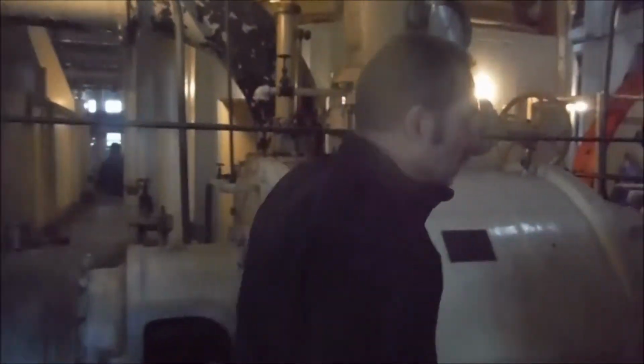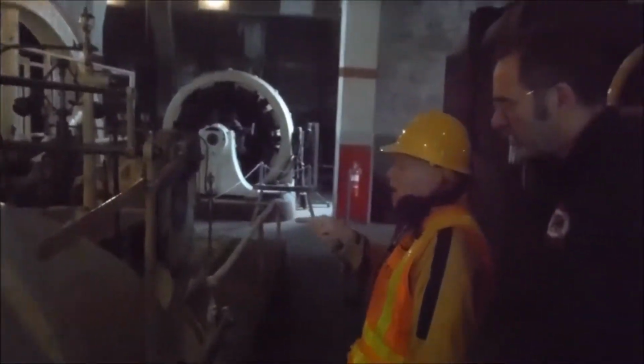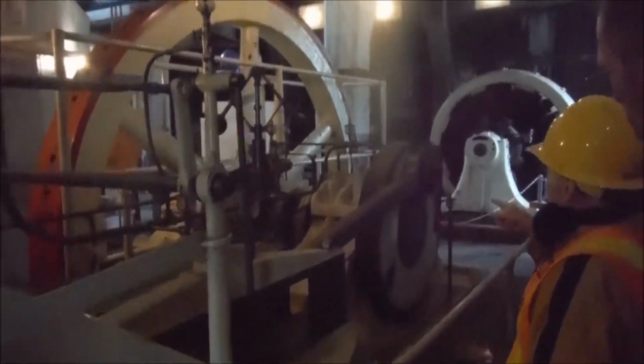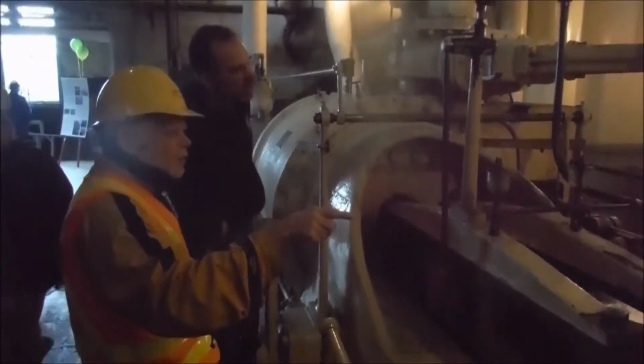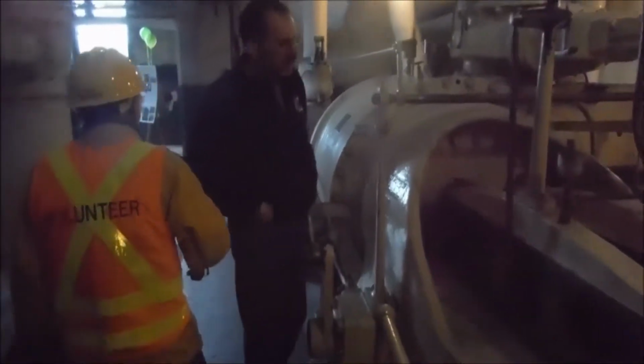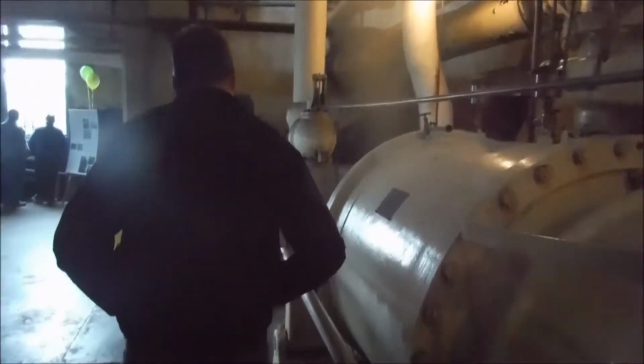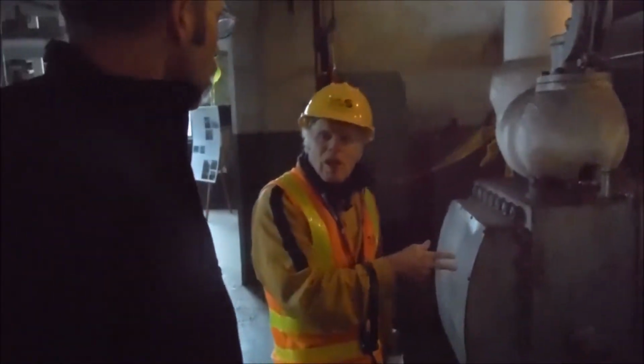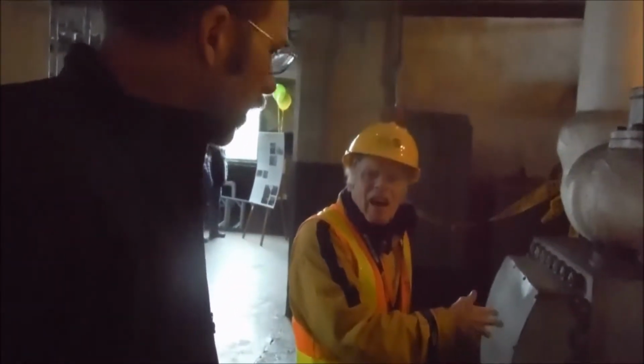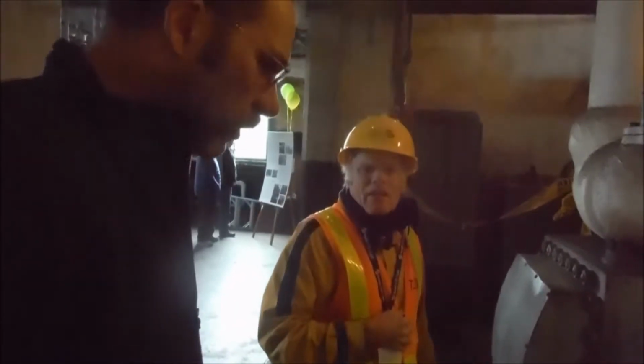The shaft comes out of the opposite end of the pump and continues to a crosshead, then a connecting rod to an eccentric shaft and the flywheel. There are two eccentrics: one operates the valve here to switch the port when the piston finishes one direction of travel. It shuttles the valve, switching ports to direct steam to the other side of the piston, while the previous side goes to the outlet. So this rocker and these arms are controlling the valve here.